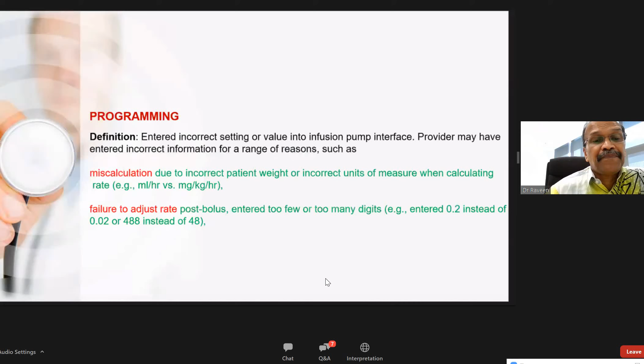There's a miscalculation. Or failure to adjust the rate. So you start with the bolus and then you forgot to adjust the rate for after the bolus has entered, what is the maintenance rate? So you might have entered 0.2 instead of 0.02. Or instead of 488, you enter 48. Or the most common mistake is 5 and 50, the one digit difference. So these are the common errors to make in the programming, where the person who is going to use the pump enters the data into the pump.